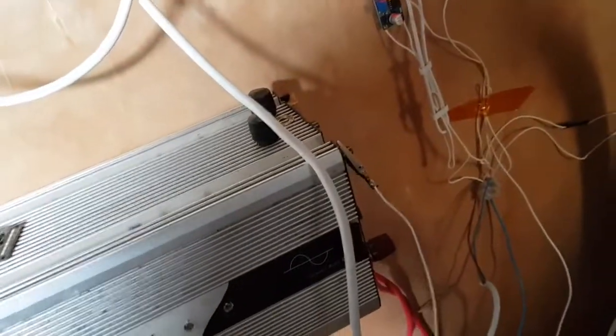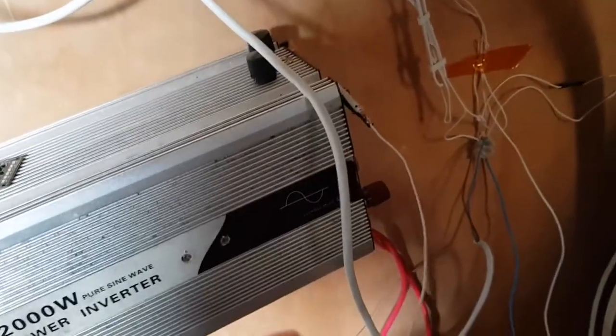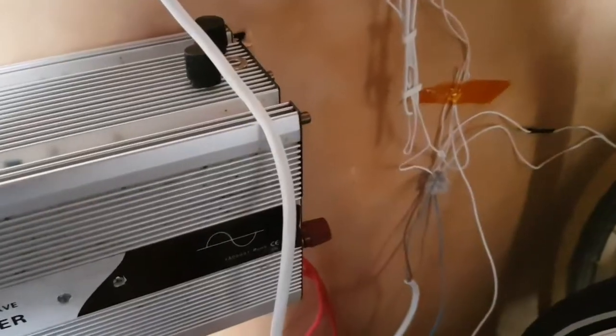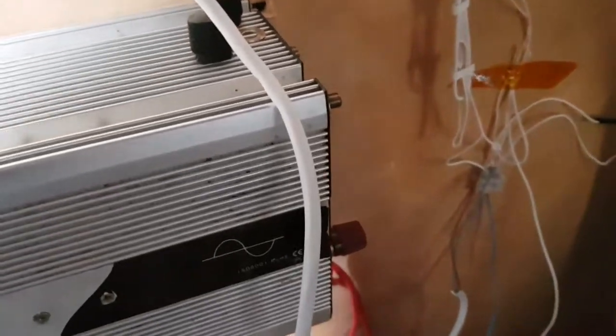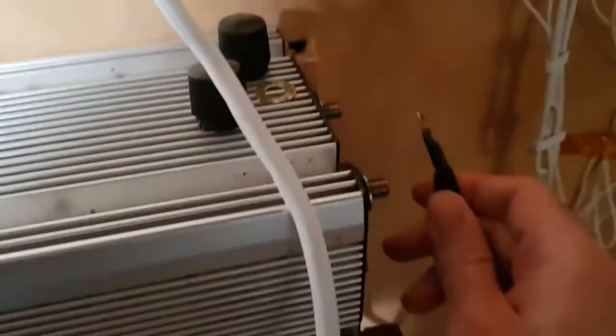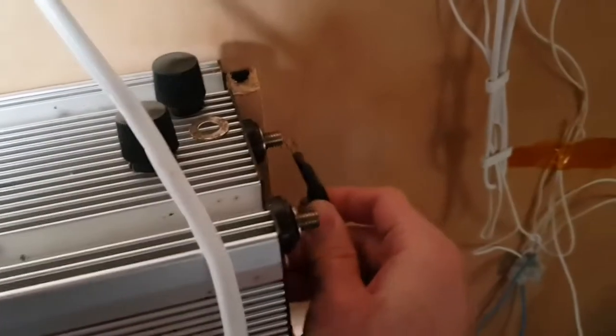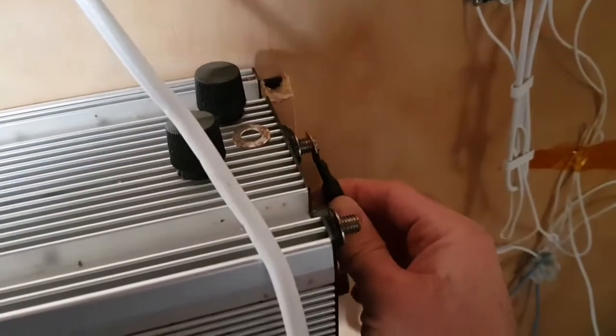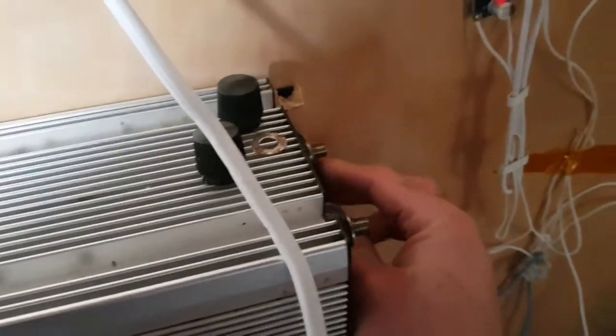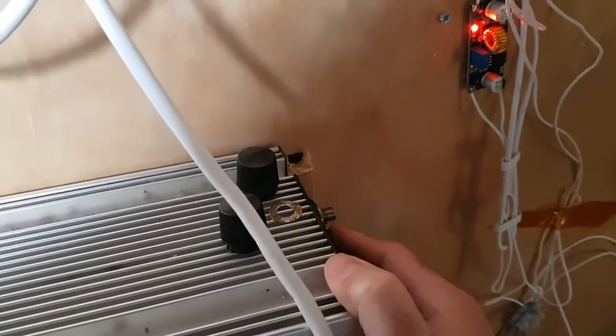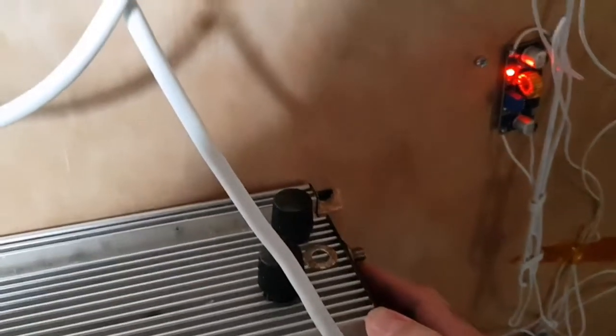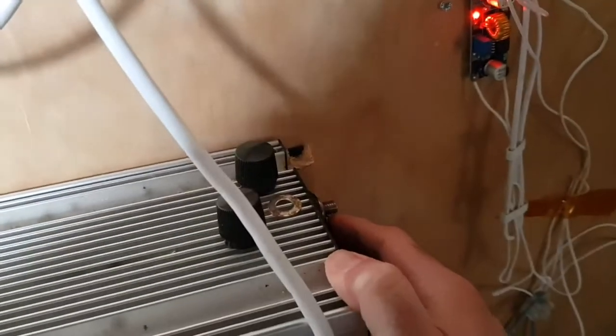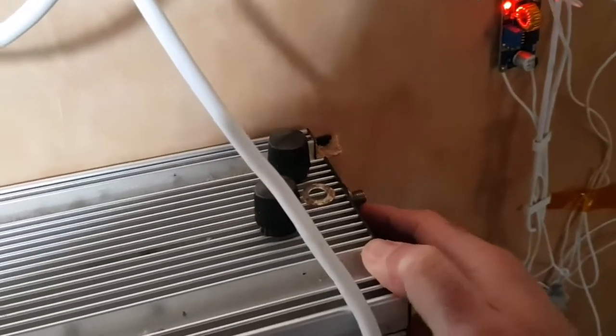So now I can use my power resistor on the back of the inverter to charge up the inverter, so I don't get a big spark. My hands are too short while holding a camera, so I'm going to have to do this off camera. That is now charged. I can now take my leads and safely connect them with no spark. There you go, no smoke whatsoever.